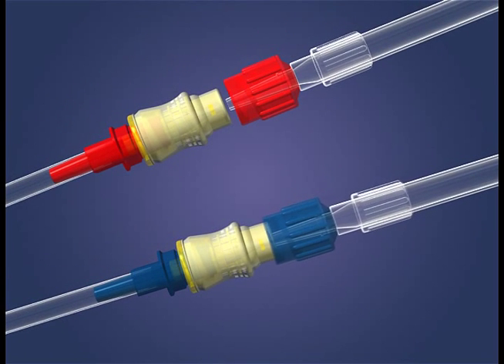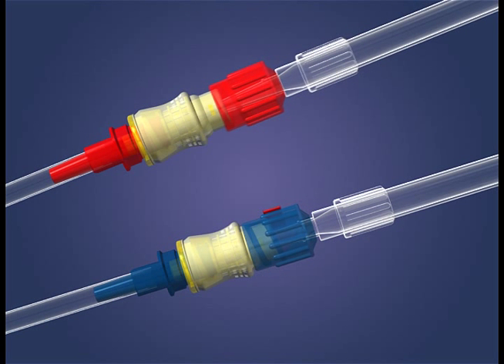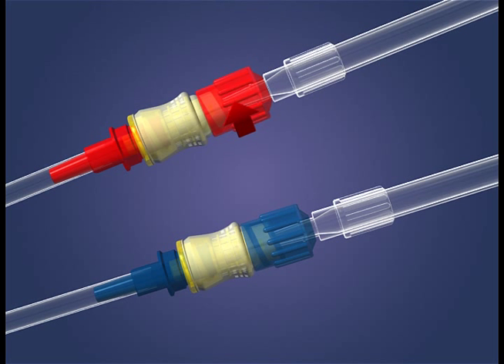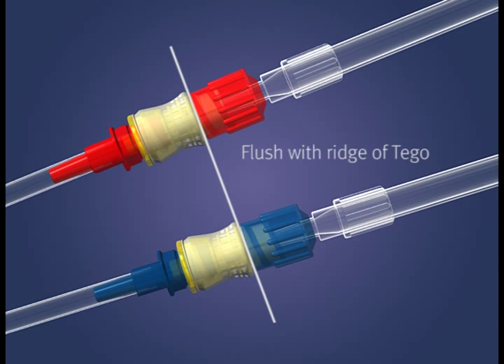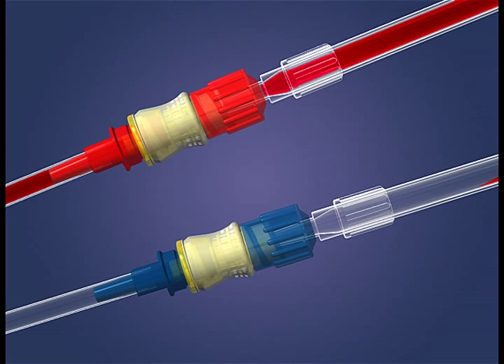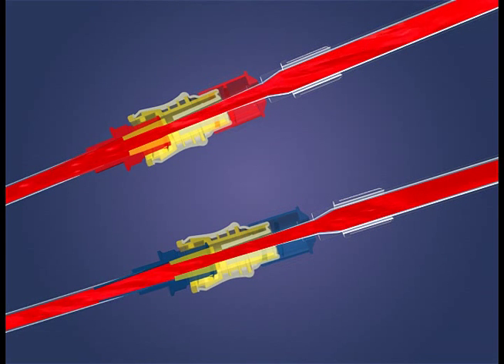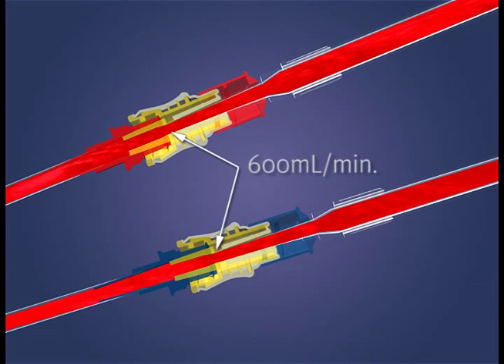By grasping the rotating collar, push and twist the bloodlines into the Tego until secure. Be certain you have a secure connection, but do not over-tighten, as this may damage the Tego. The end of the collar should be flush with the ridge of the Tego. You can now begin your hemodialysis treatment. The Tego has a unique straight-through unobstructed fluid path, which is critical for maintaining the integrity of the blood while still providing a flow rate of more than 600 milliliters per minute.